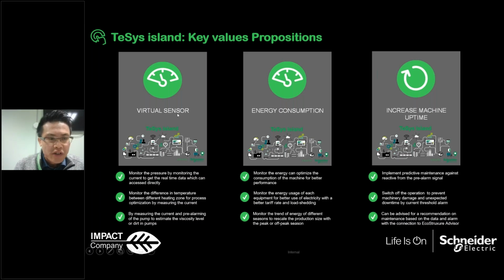First is the virtual sensors. What does it mean? Because we monitor the current of these individual motors, by monitoring the current you can basically estimate the temperature change or the pressure of the system. If the temperature of the motor goes higher and higher, the current will go higher as well. This is the relationship between the temperature and the current. When the motor is much hotter, sometimes an overload occurs in the motor, so the current will go high as well. So by monitoring the change of the current, you can estimate the temperature of the motors. This is what we call the virtual sensors.